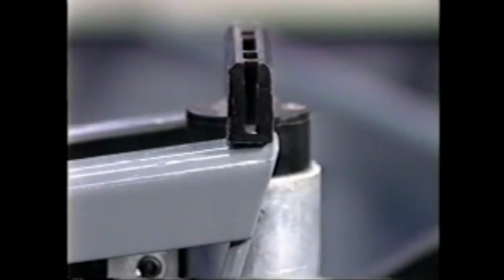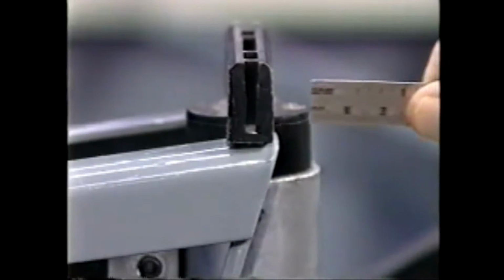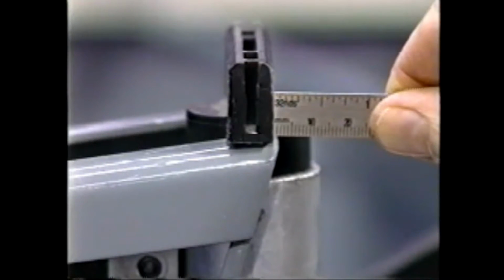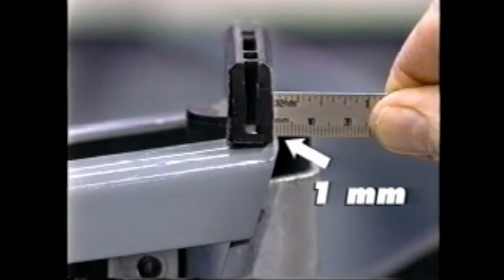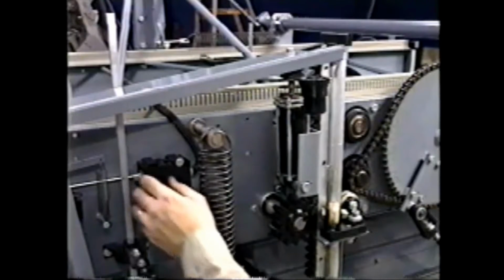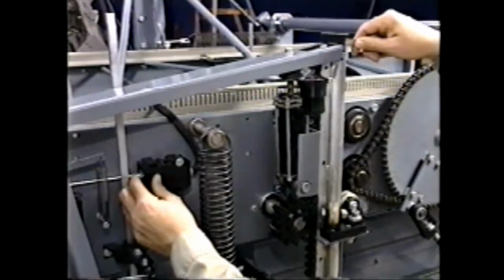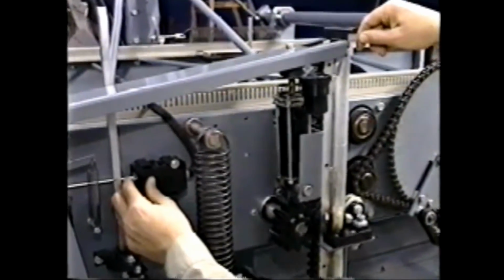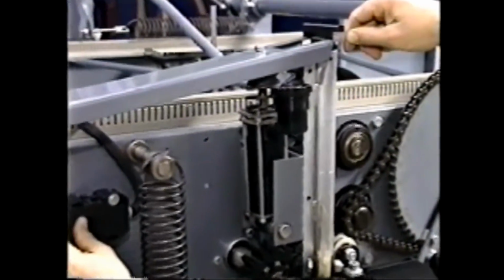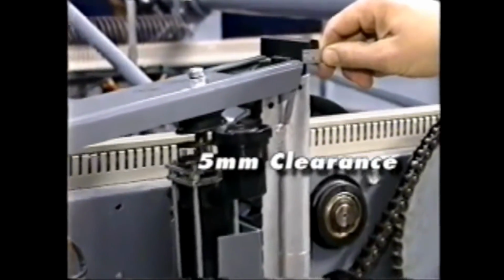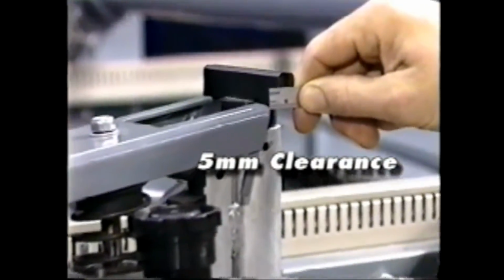The stroke limiter plate adjustment is checked by manually lowering the table until the stroke limiter T-stop barely touches the stroke limiter plate. There should be a 1 millimeter protrusion of the plate beyond the T-stop. This can be adjusted using the small bolt on the bottom of the limiter's vertical arm. Next, manually press the plunger of the limiter solenoid to check for a 5 millimeter clearance. This adjustment is done by loosening both solenoid mounting screws and positioning the solenoid properly.